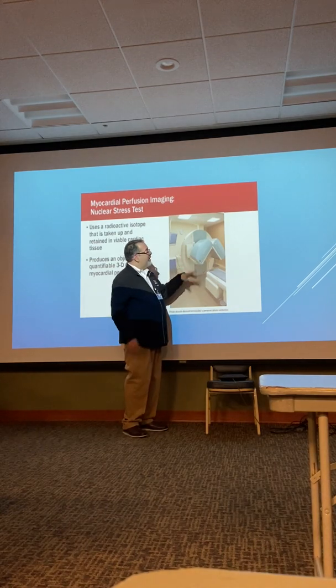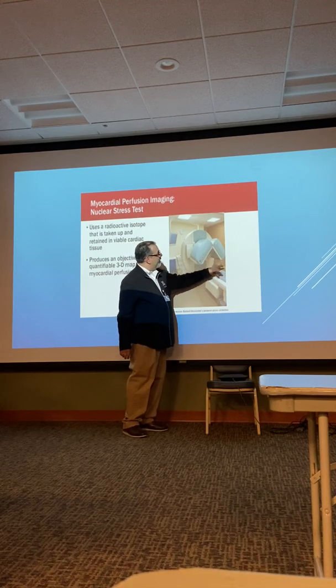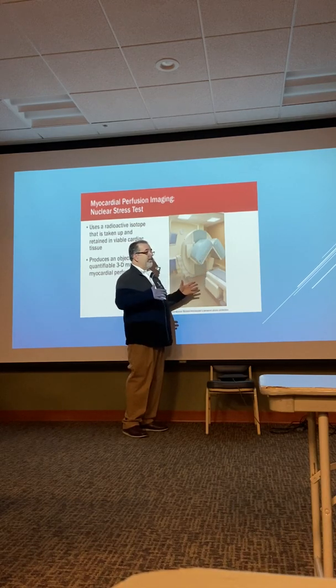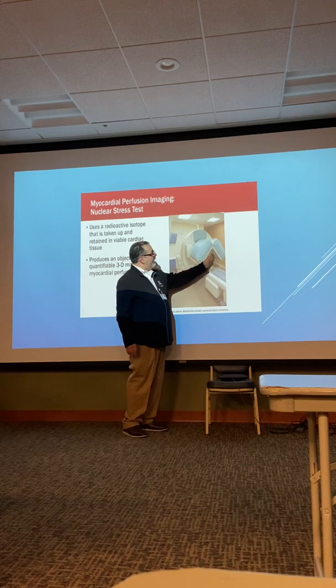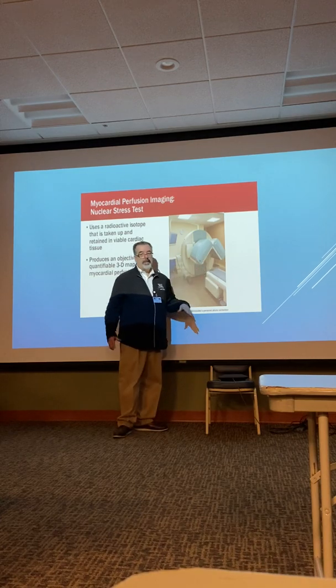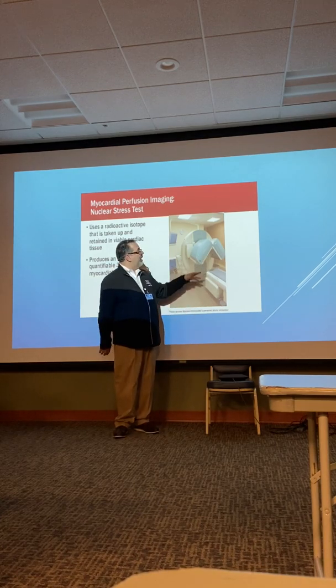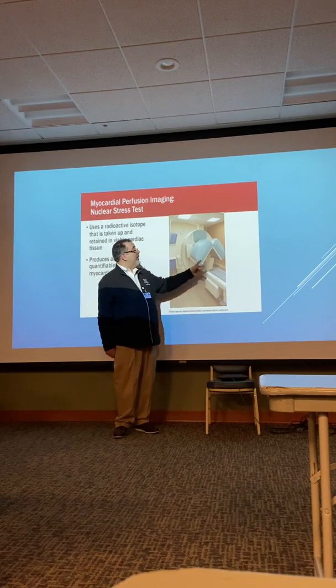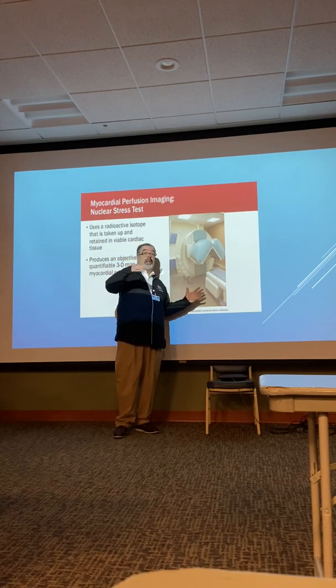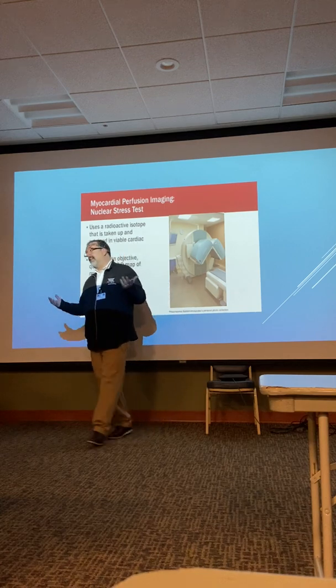Each of these heads has a filter on it to focus the radiation coming out of the patient and coming to the camera head. So they're called collimators. The collimators are on the heads of the cameras, and the patient lies on the table and the radiation is being emitted, and each head of the camera is reading the information, and then it moves around the patient. There's 64 pictures, but because there's 2 heads, it's 32 stops. It stops 32 times, and usually each stop's about 25 to 30 seconds. So that's one of the reasons why the patient's down there so long. The major reason is transport sucks, but that's another thing.